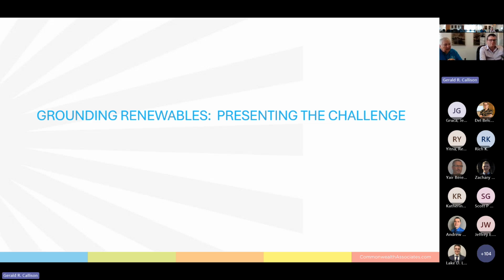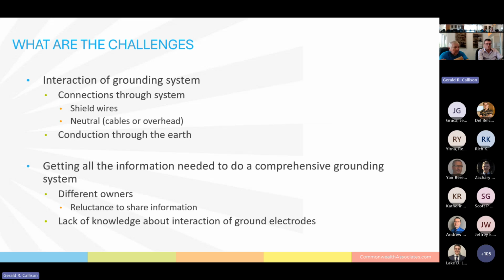Thanks, Gerry. So we're going to talk about grounding renewables and present some of the challenges that take place when you have a situation where you have a number of different grounds located relatively close together. So what are some of these challenges? Well, what we need to know is that there is an interaction between grounding systems. And the grounding systems typically are connected through, as Gerry described, shield wires or neutrals, and those neutrals can be in cables or overhead conductors. But there's also conduction through the earth, which ties the grounding systems together.